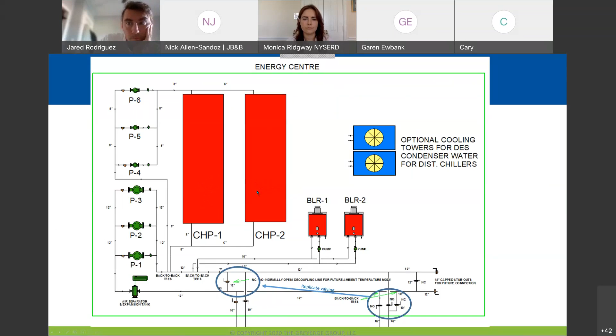So this now becomes effectively a large boiler injection loop if I need extra heat or want to utilize it. By the way, the CHP generated here tends to offset all of the cooling costs in this situation, and it's about a quarter of the total electric load. So we were able to mitigate approximately 50% of the high temperature load and all of the cooling load because of the electric generated.